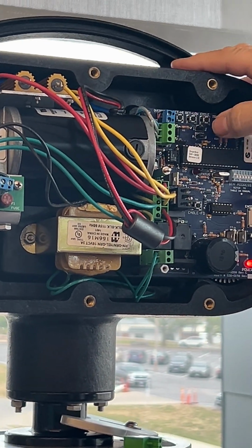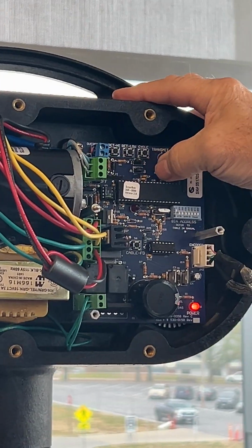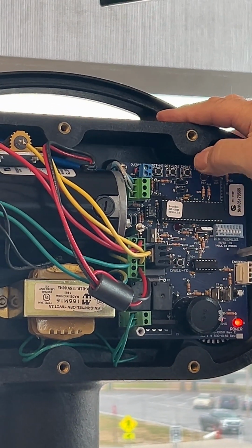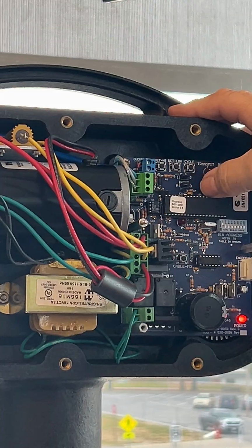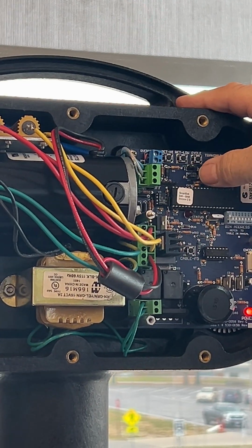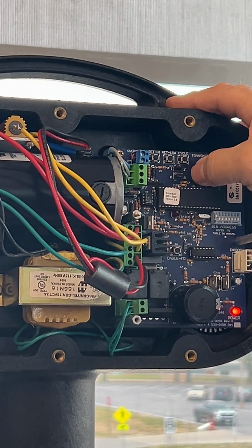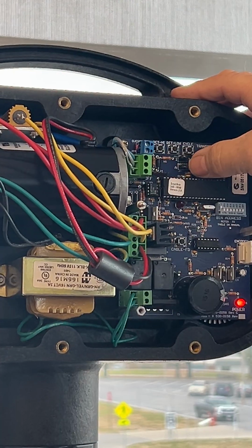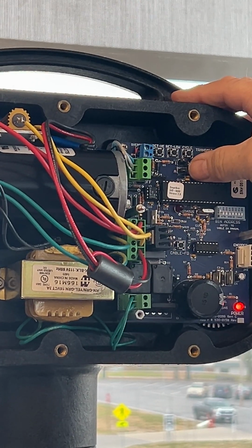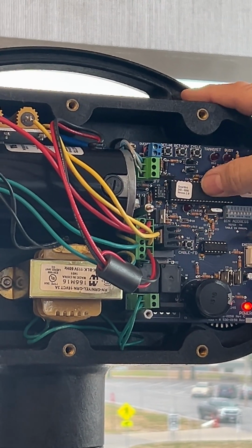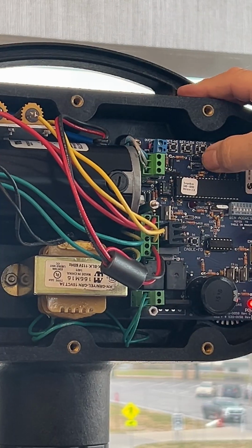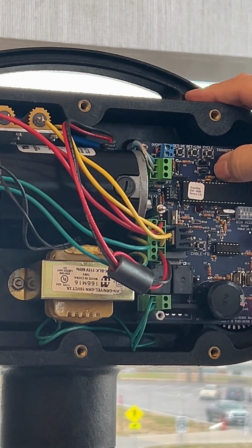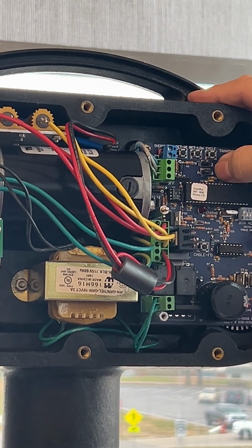The other thing to check is your protocol jumper right here. Just below these 3 push button switches, there's an A position on the left and a B position on the right. Most everything anymore is in the A position. That's what we send them out in. That's our newer protocol. Our very first SmartBob designs would have been in B protocol.